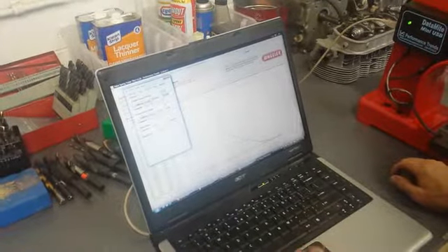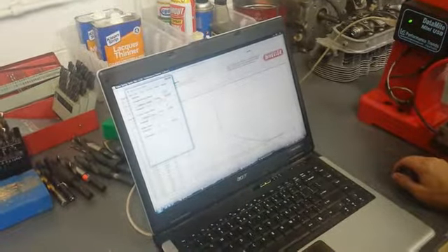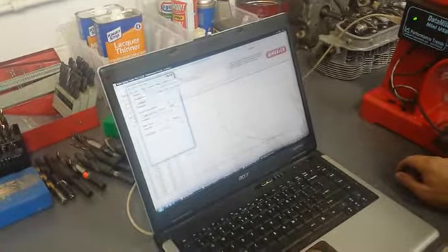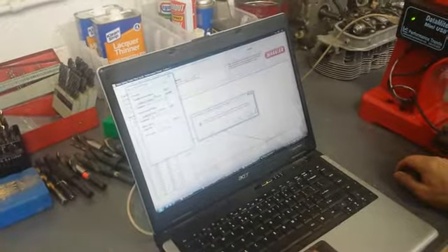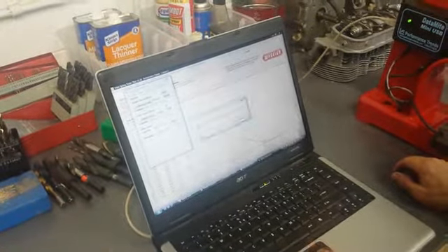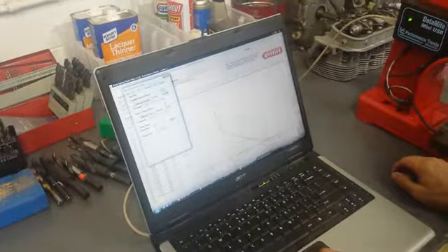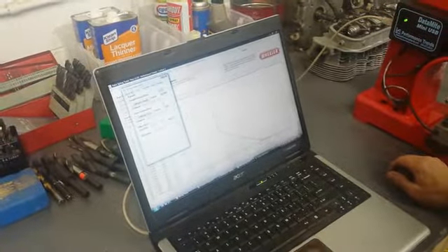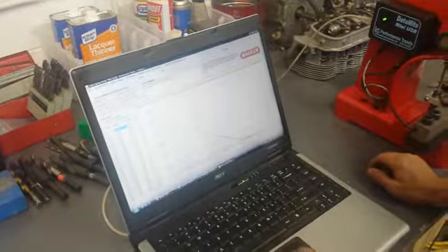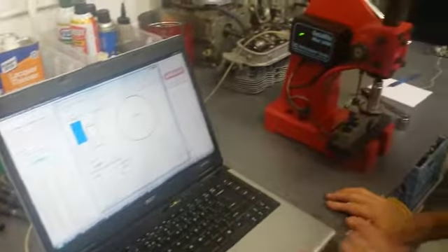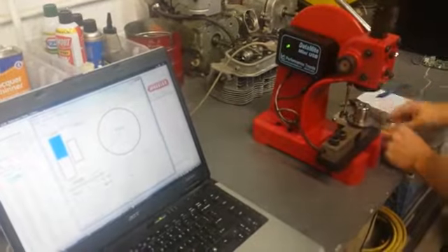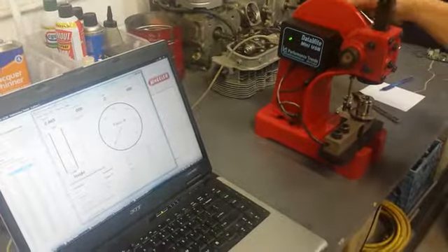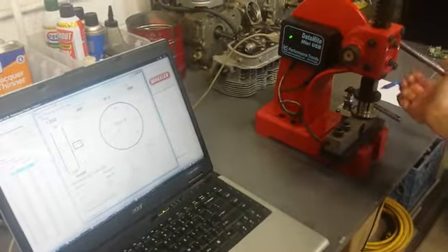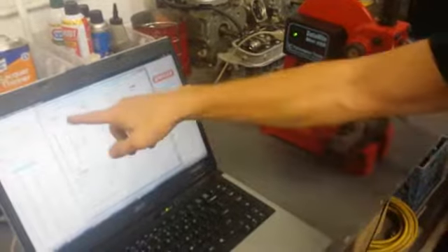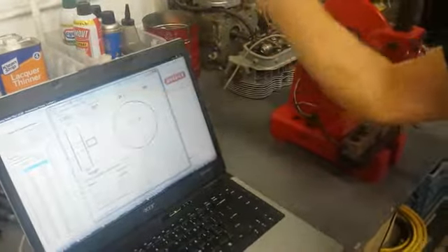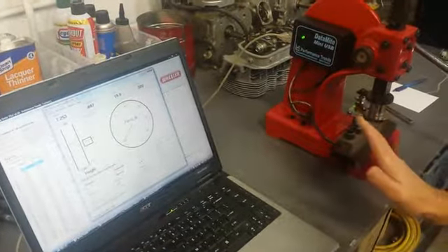Yep. And now it's loaded them in back here, and I'm going to say File, Save as my master settings. Yep, I want to do that. They've been updated and saved. And now what you want to do is just double check that things are making sense. You go back to the recording screen, and for example, let's go back to the 1.253. This thing should read 1.253 when it's on the sensor, on that standard, and you can see it reads 1.253 exactly. So you know you got a good calibration.